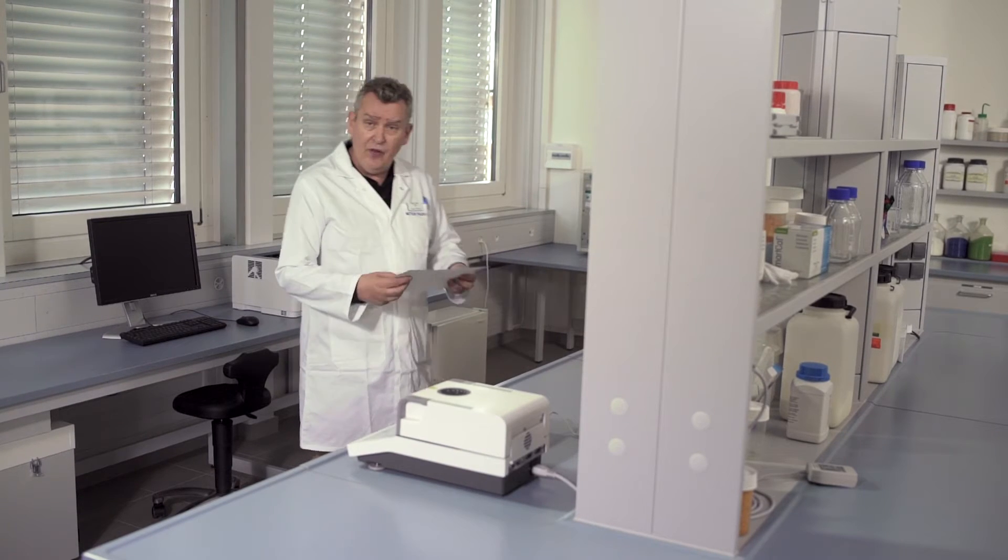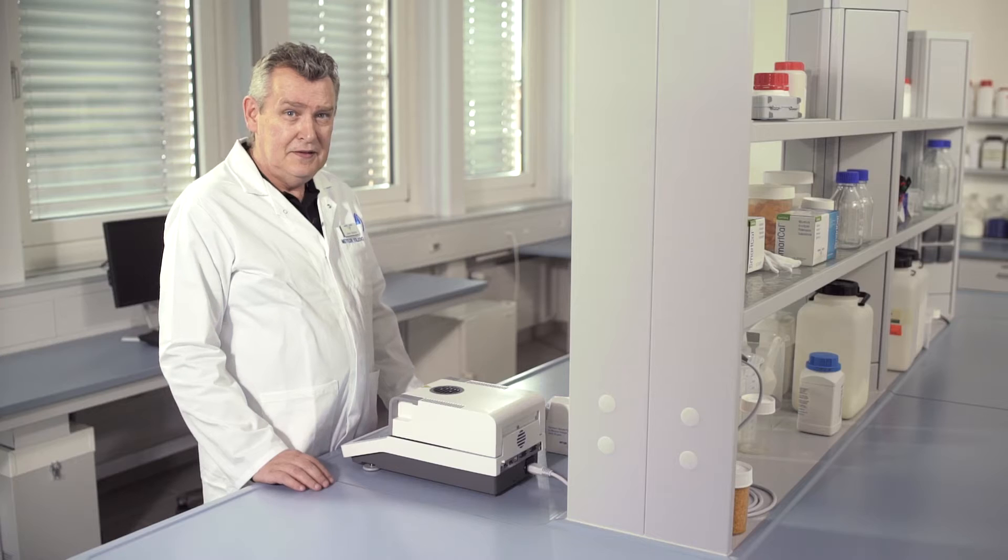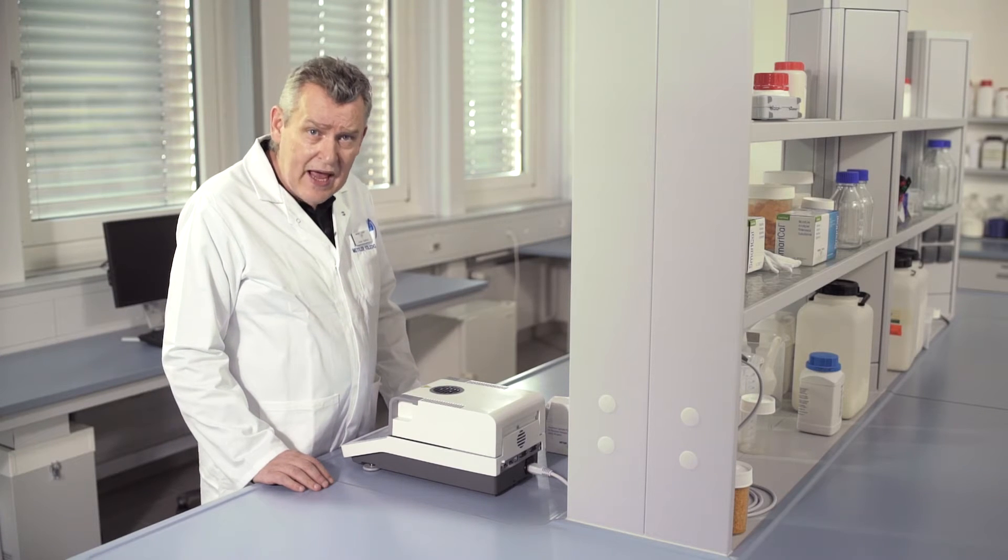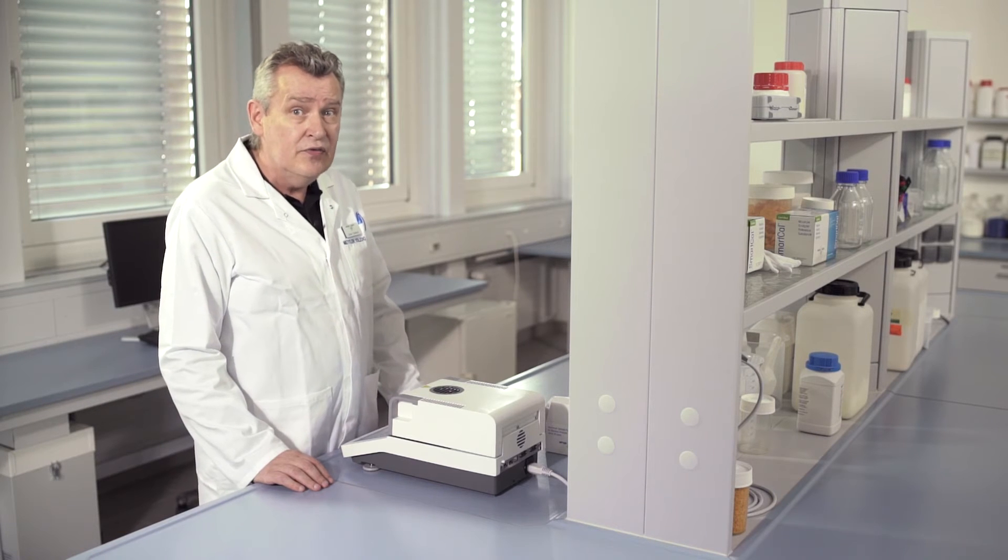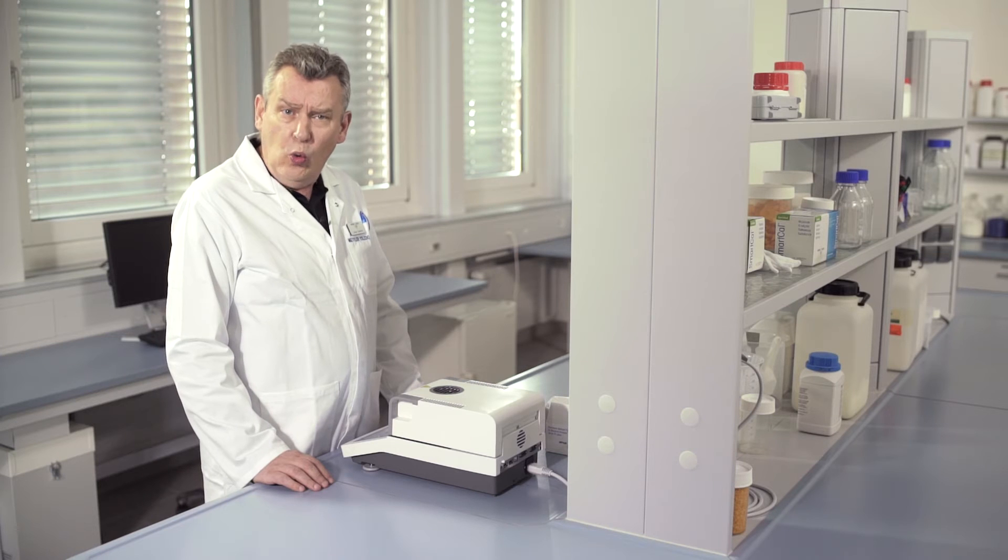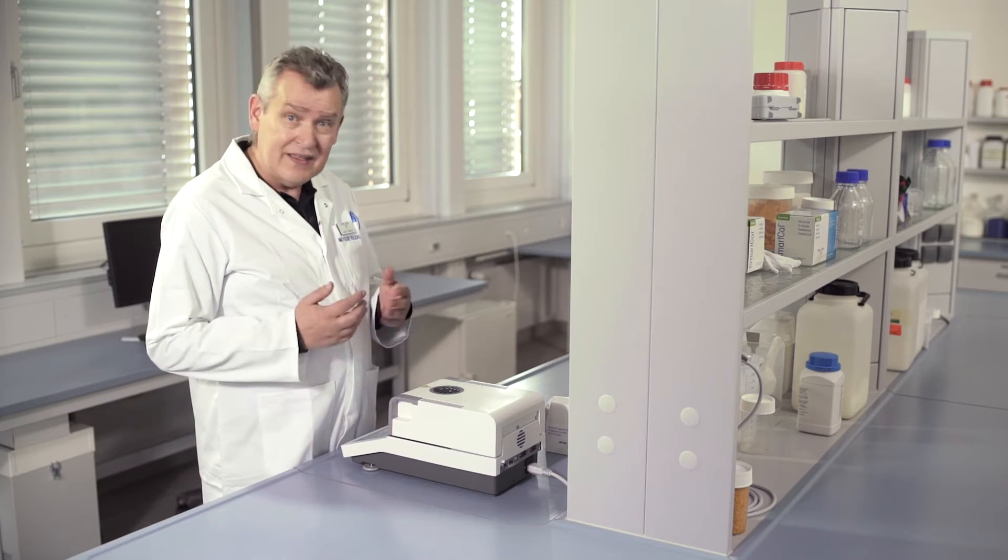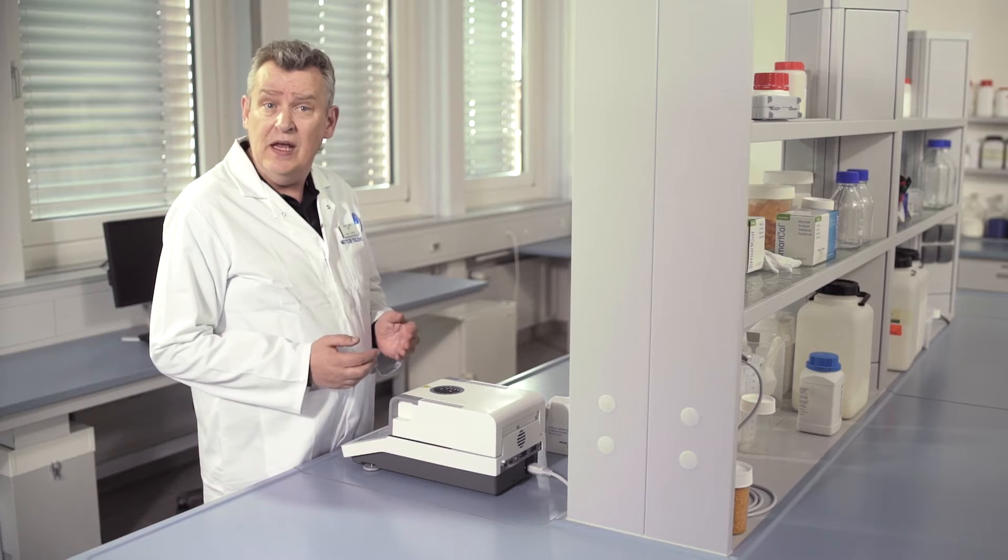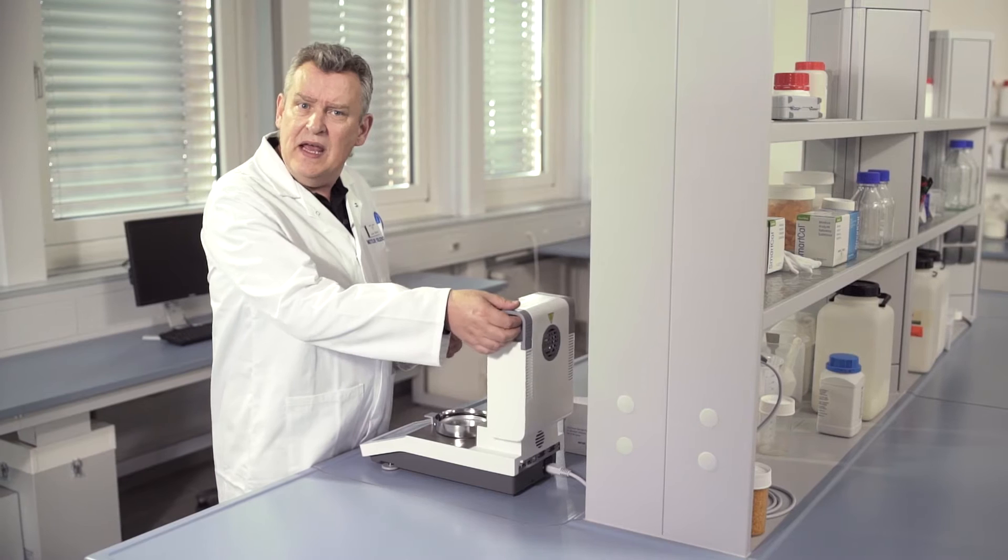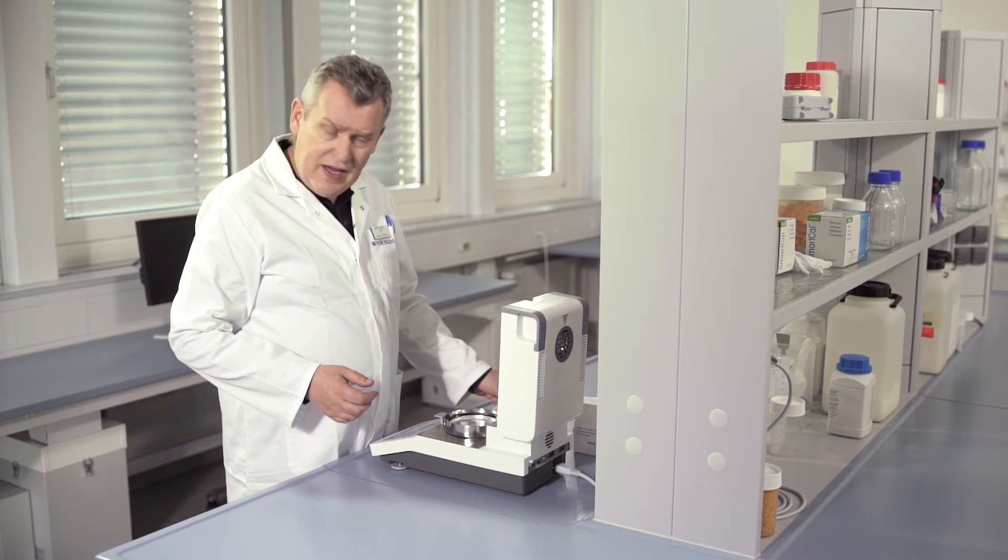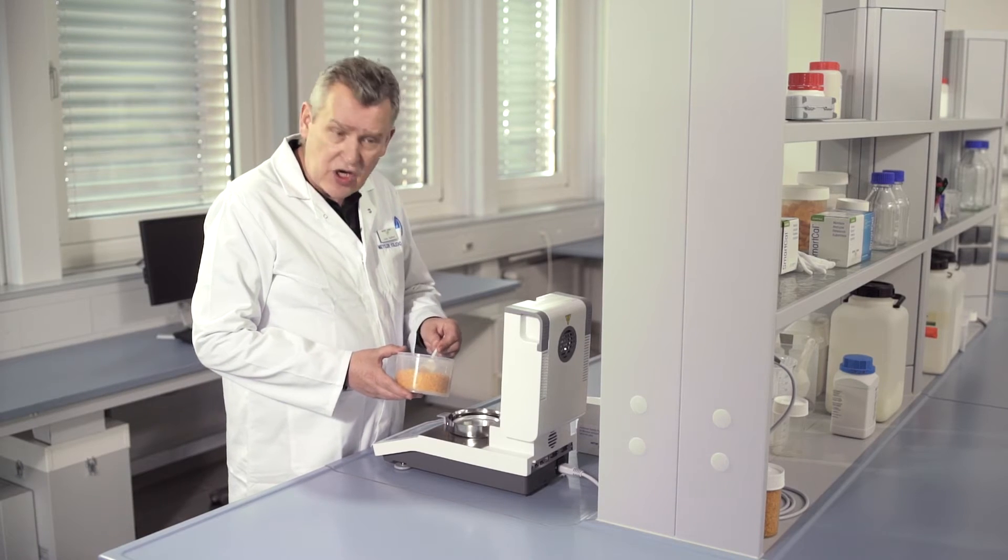Correct sample preparation and careful handling is the key to getting repeatable, accurate results. Always try to weigh in the same amount of sample, typically between 3 and 5 grams. You don't have to be exact, but it's a good tip to try and weigh in the same amount each time.